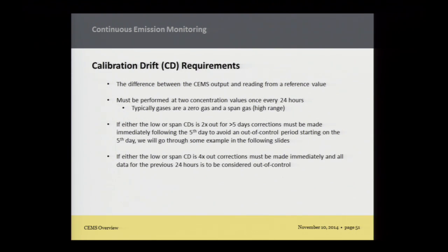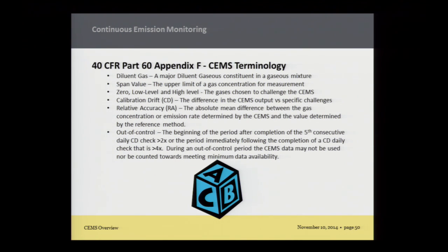Actually, in that particular appendix, I think it says also if you drift 2x, if you fail 2x, you're supposed to correct it. You're supposed to make an adjustment, make an effort at an adjustment. So later that day, we had an analyzer tech go look in the building, and he looked at the analyzer. Did he try to make an adjustment? I don't know. We typically would just go back to the logbook and try to document that. I haven't seen places take a deviation for not attempting to make that adjustment on day 1, but I know that it happens a lot that, oops, I was gone Thursday, Friday, Saturday, Sunday, and I came in Monday, and you hadn't gotten to out of control time yet, but you didn't make an attempt on Thursday because that was my unit and I was on vacation and I didn't ask anybody to cover it.